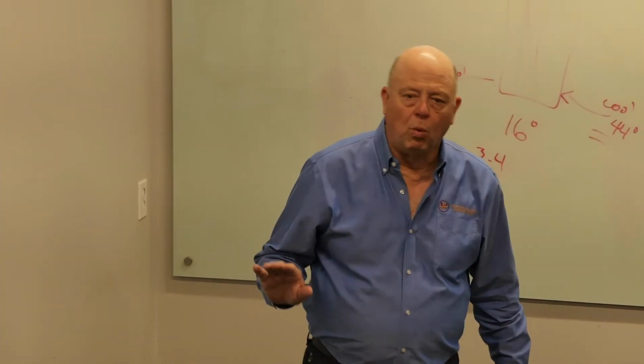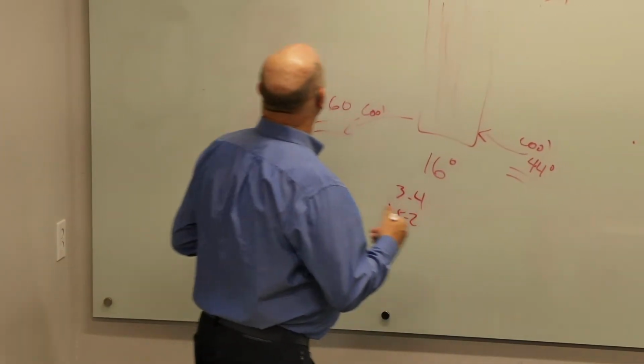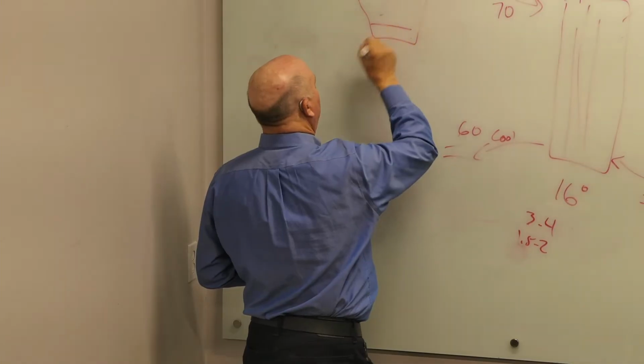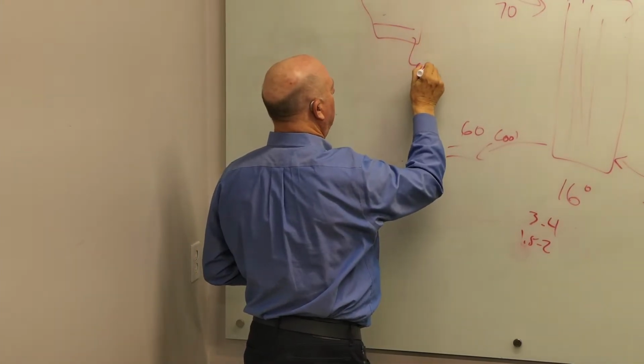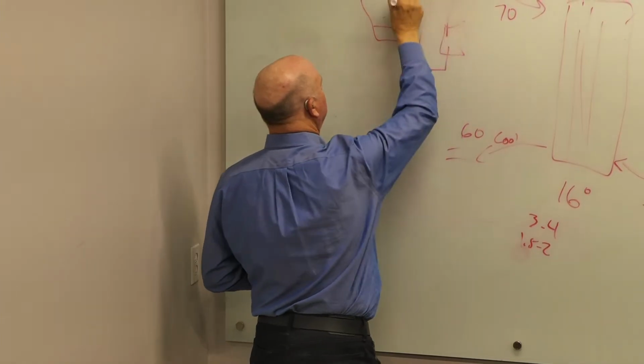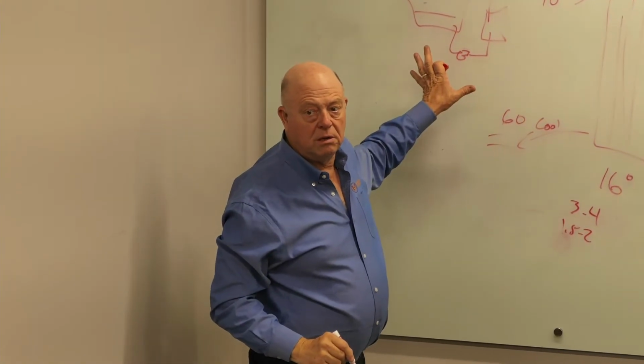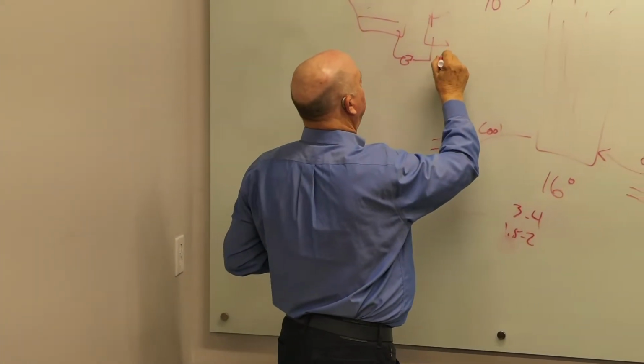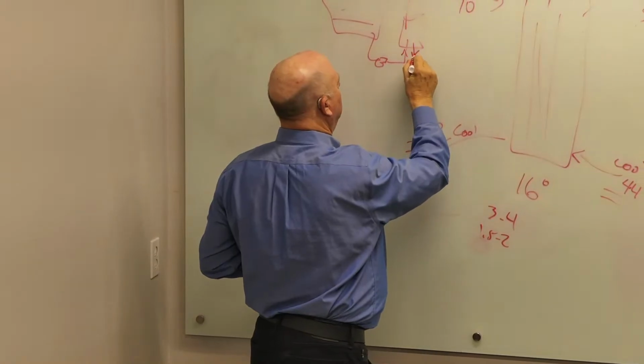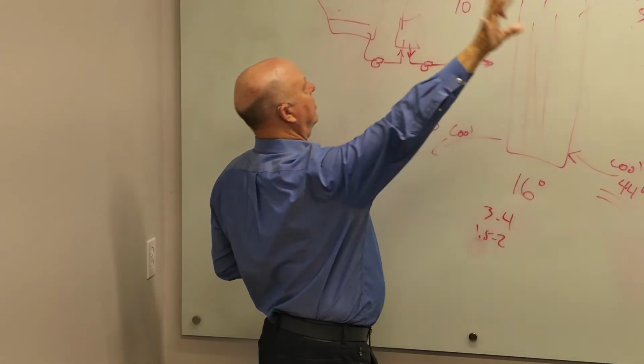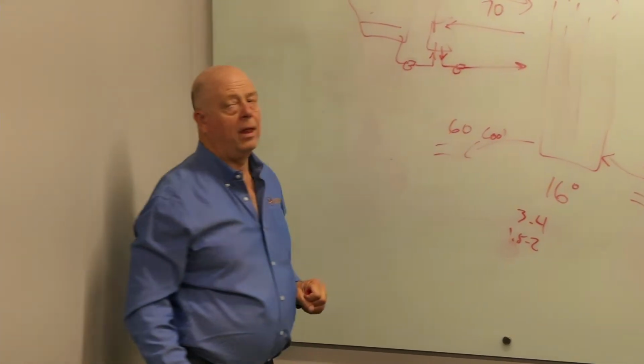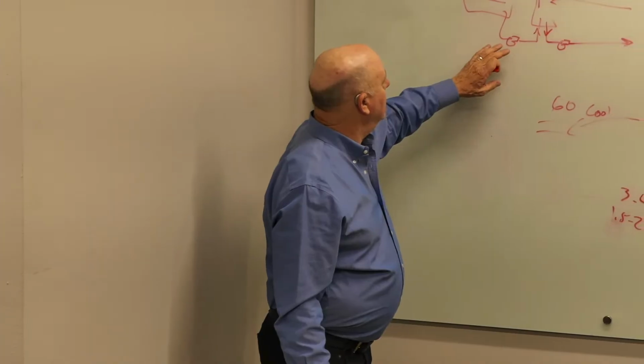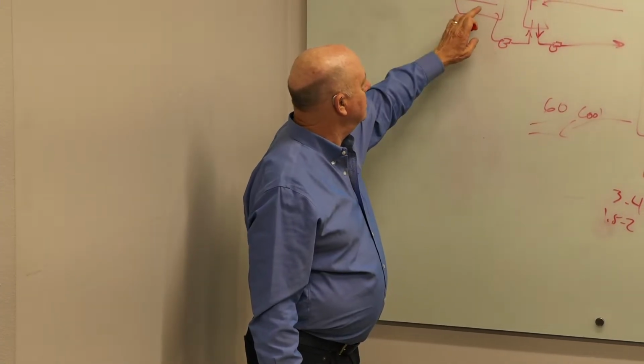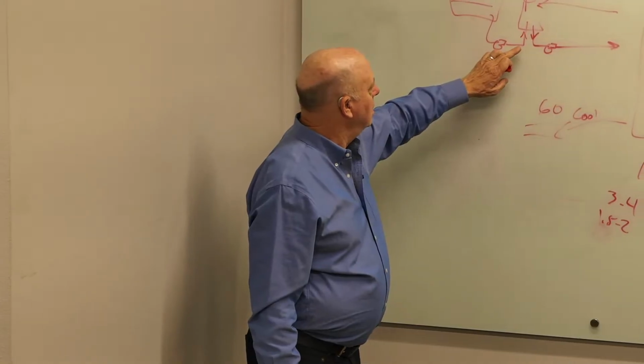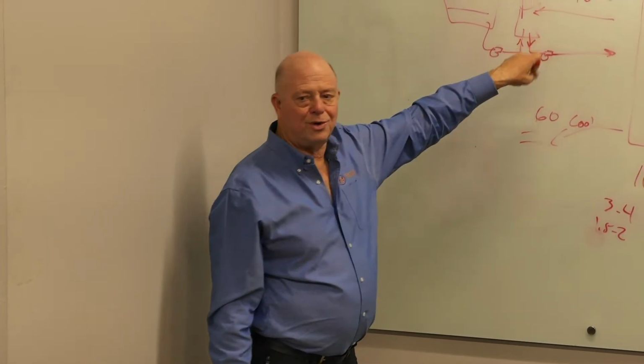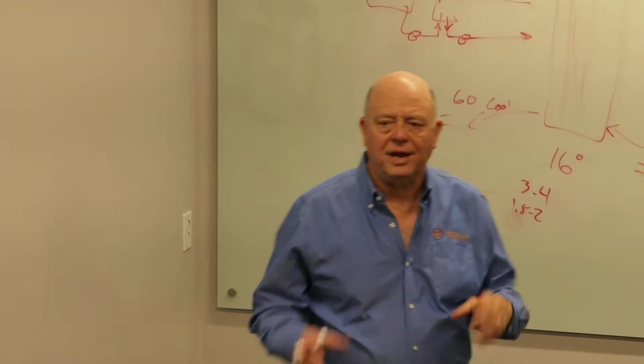And so the workaround, if you want to be cheap, is you use an open tower and you have a pump that just takes the water to a plate heat exchanger and then dumps it back in the tower on one side. And then the loop going to your water source heat pump building goes out to the building and comes back. Did I do that right? This is the cooler. I think I circulated that wrong. I don't think I have counterflow, but I'd have to look at it and think about it.